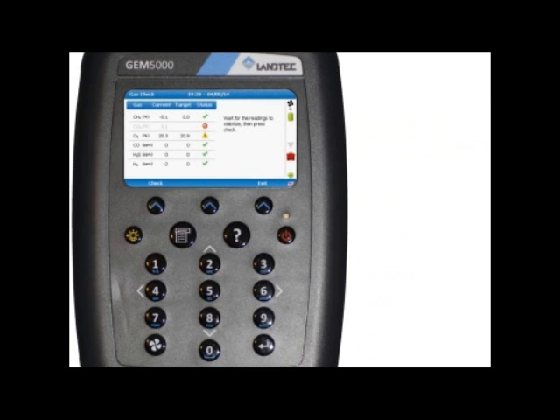After selecting the fresh air gas mix, it will take you to the gas check screen. And by default, the pump is configured to automatically turn on and to pull ambient air. At this time, wait for the values to stabilize, and then using the left soft key, select check. This will activate a 1-minute timer. During this period, the gas values will finalize stabilizing.